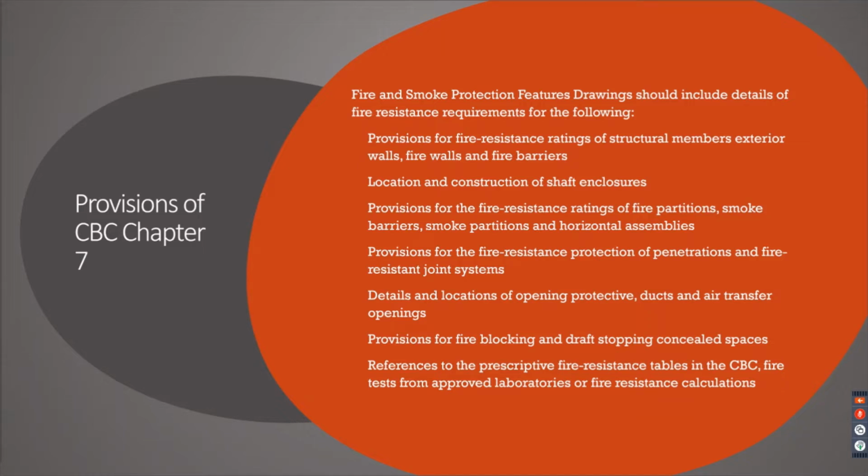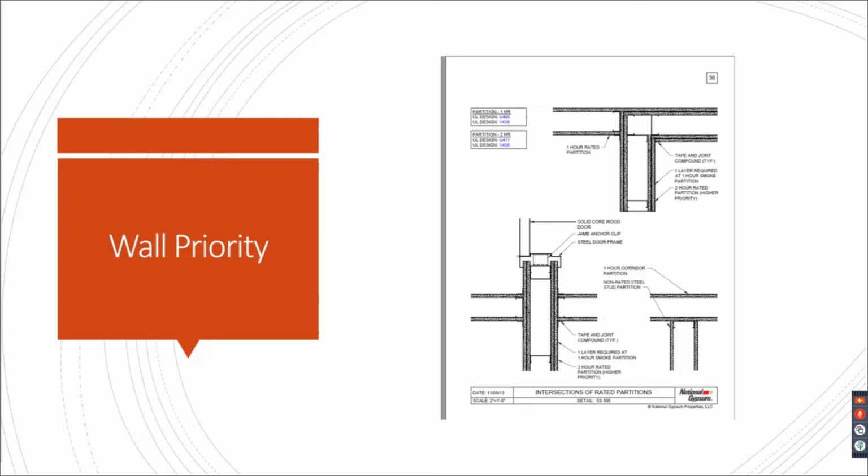Usually, and just as a side note, if there's a listed approved assembly, that listed approved assembly is what is to be used. There are allowances, as you know, with EJs and using the table, of course, those are in there. But if there are listed approved assemblies, then those are to be used. The others are options if you can't find one. But we'll have a whole different webinar on EJs, so I won't get into that too much.